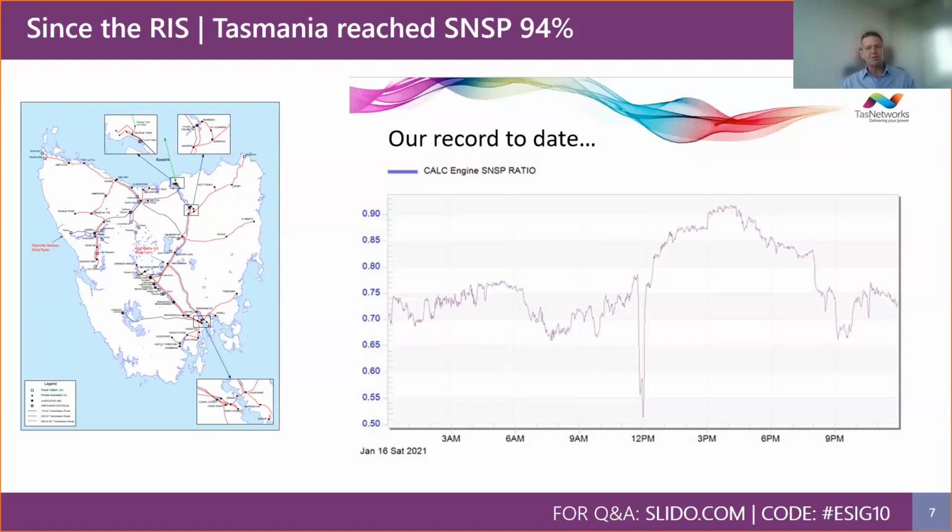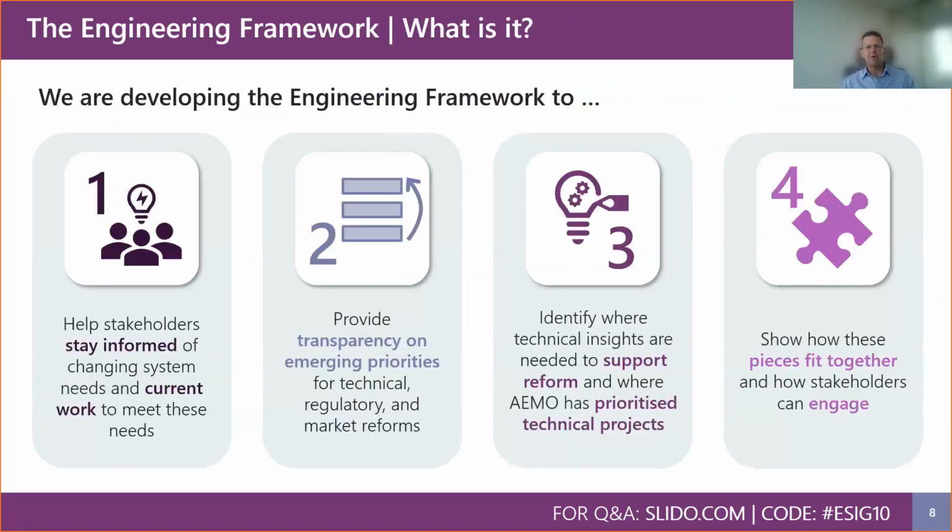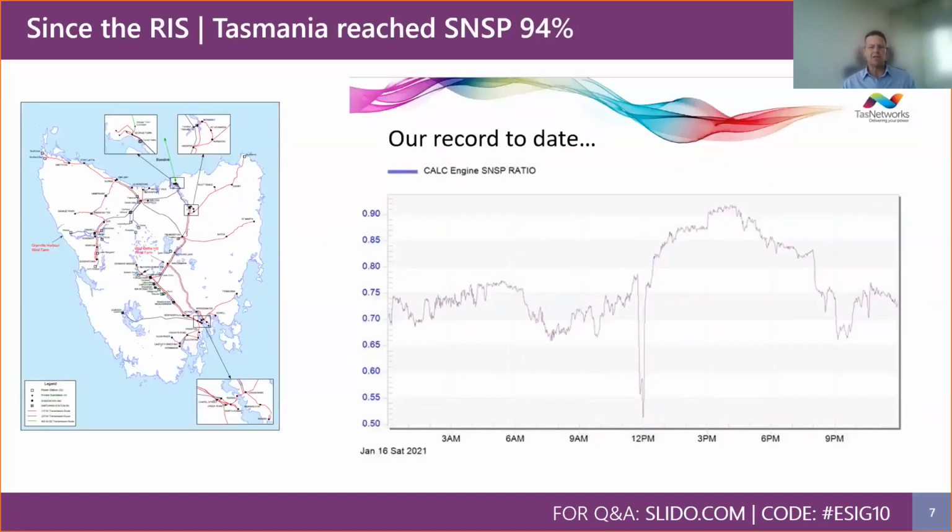Tasmania is also blessed with exceptional hydropower opportunities, both run-of-the-river and storage, and many of these units are clutched and can operate as synchronous condensers to support the system without having to be generating power, which certainly has helped to increase the SNSP levels. Solar generation is limited in Tasmania, being one of the southernmost states.